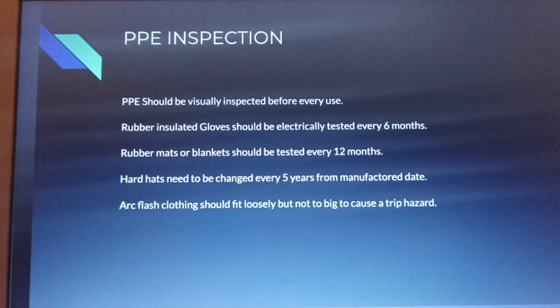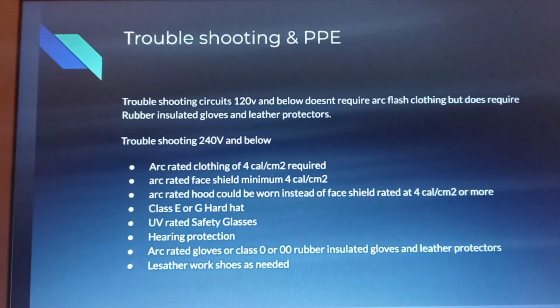And then the PPE inspection. PPE should be visually inspected before every use. Rubber insulated gloves should be electrically tested every 6 months, as well as the visual test every day before use. And then rubber mats and blankets should be tested every 12 months. And hard hats need to be changed every 5 years from manufacture date. Arc flash clothing should fit loosely but not too big to cause trip hazards. And then we're going to get into troubleshooting and PPE.